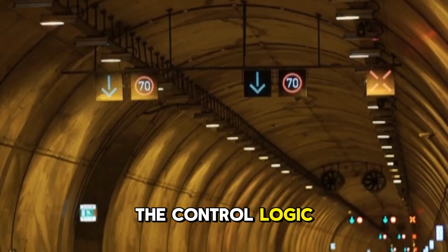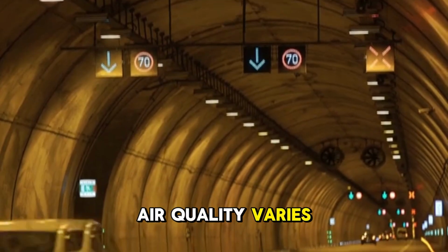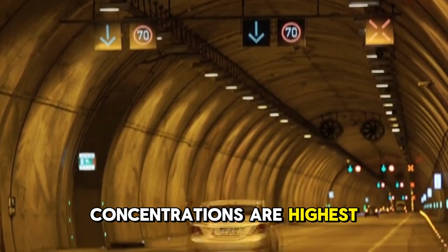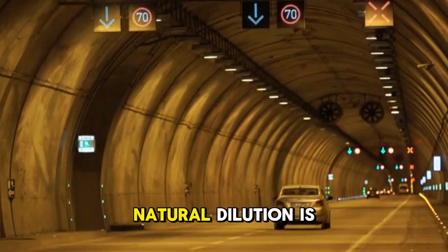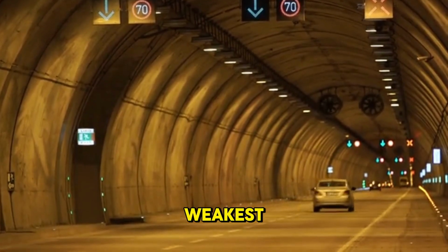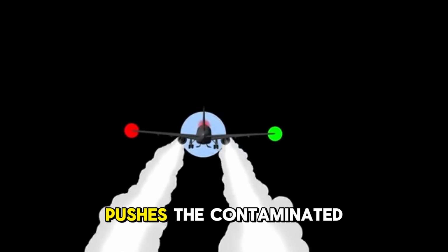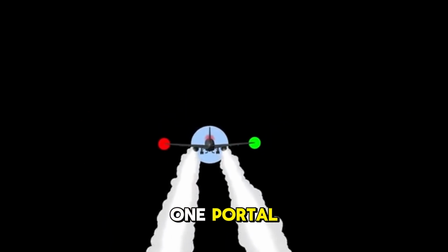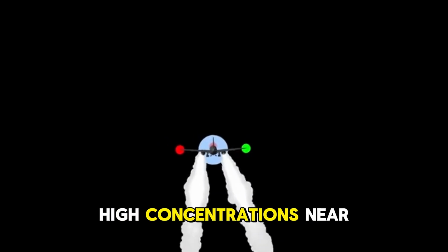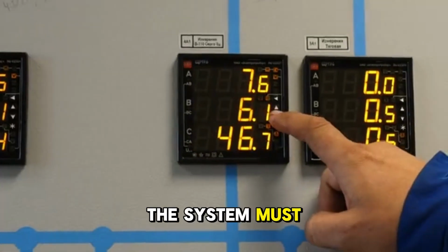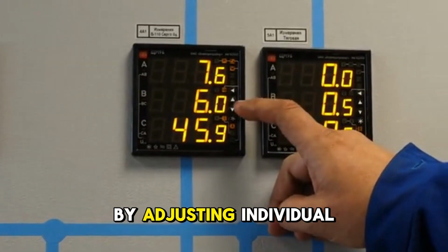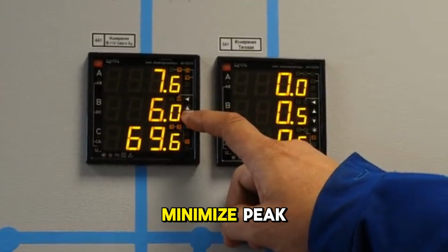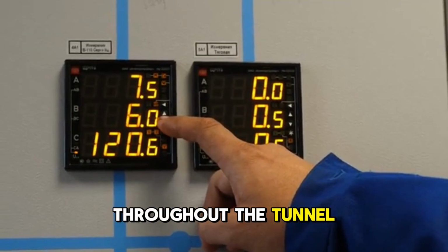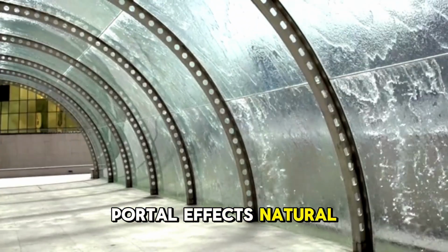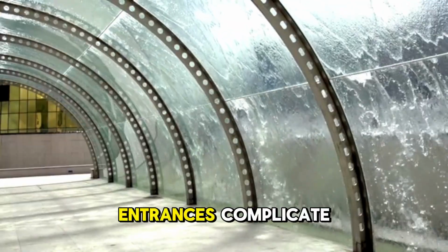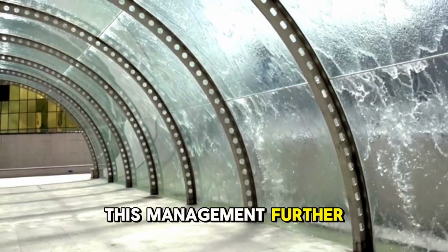The control logic is complex. Air quality varies. Concentrations are highest where traffic density is greatest and natural dilution is weakest. Running all fans at the same speed pushes the contaminated air mass toward one portal, potentially creating high concentrations near the exit. The system must manage the spatial distribution by adjusting individual fan speeds to minimize peak concentrations throughout the tunnel. Portal effects, natural airflow caused by wind at the tunnel entrances, complicate this management further.